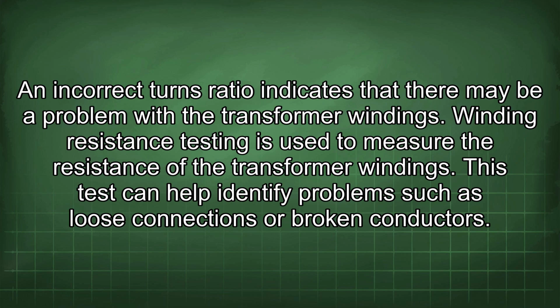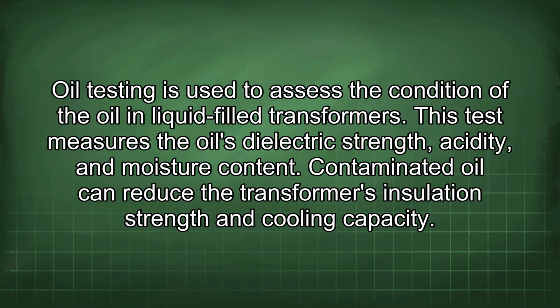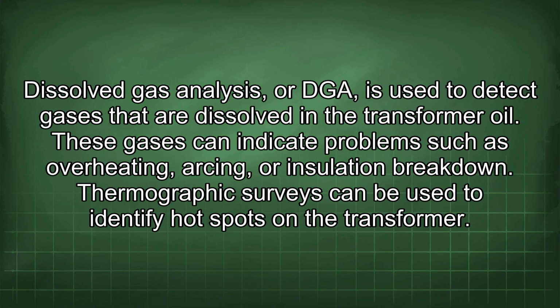Winding resistance testing is used to measure the resistance of the transformer windings. This test can help identify problems such as loose connections or broken conductors. Oil testing is used to assess the condition of the oil in liquid-filled transformers. This test measures the oil's dielectric strength, acidity, and moisture content. Contaminated oil can reduce the transformer's insulation strength and cooling capacity. Dissolved gas analysis, or DGA, is used to detect gases that are dissolved in the transformer oil. These gases can indicate problems such as overheating, arcing, or insulation breakdown.